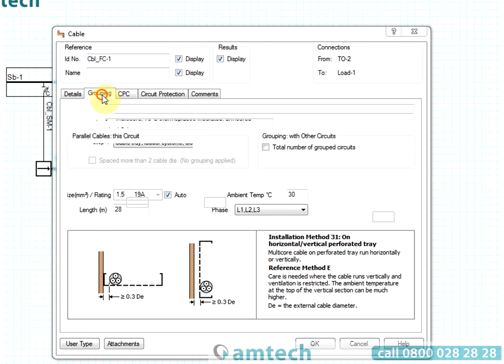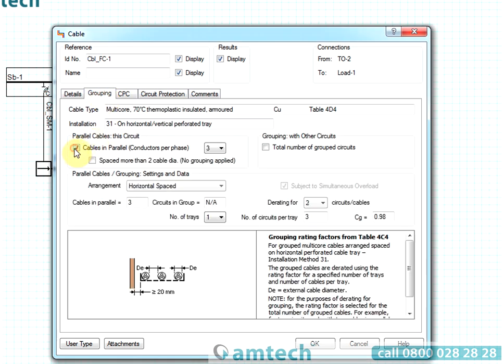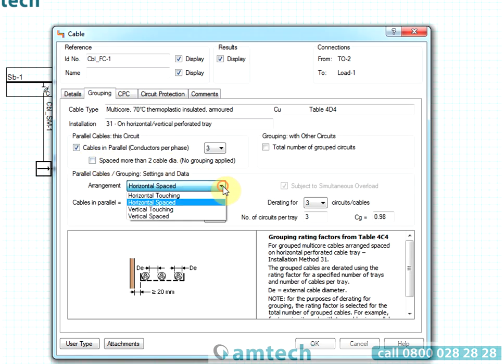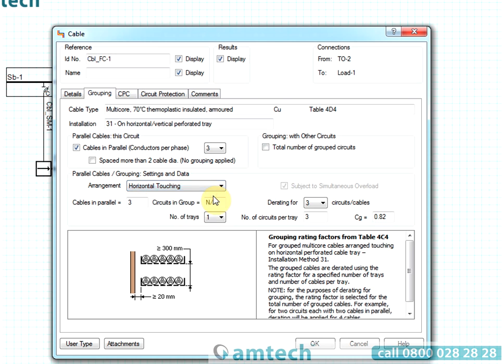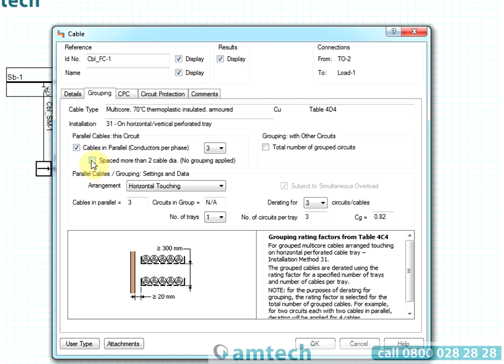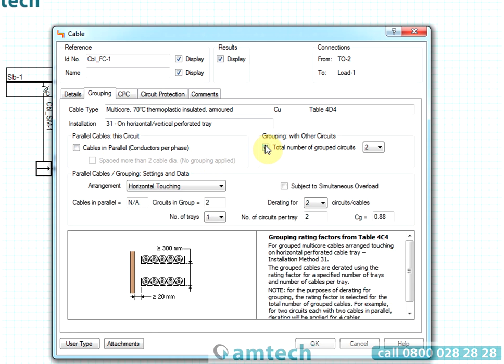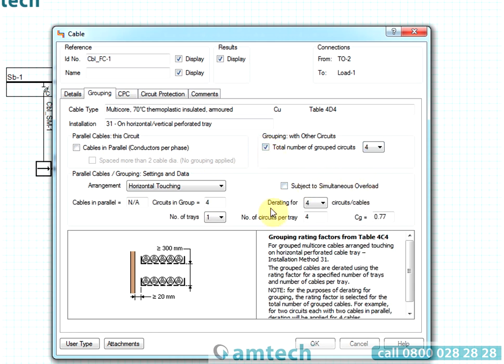An important part of cable sizing calculations is determining what rating factors to use. ProDesign uses the cable rating factor tables from BS7671, Appendix 4. You are only required to define the physical parameters such as air temperature and grouping configurations. The software will pick the relevant factors from the table for you.